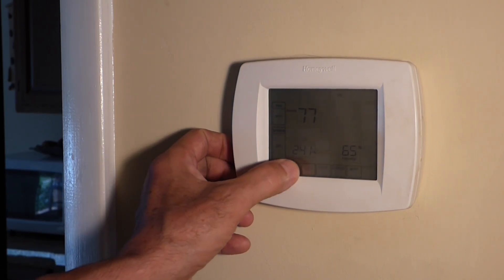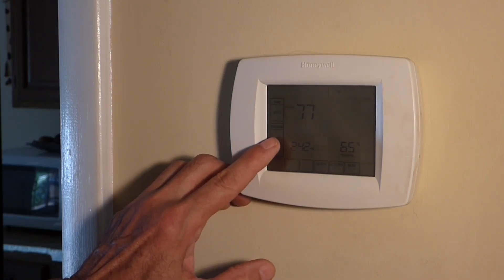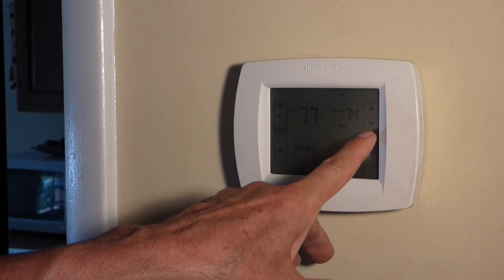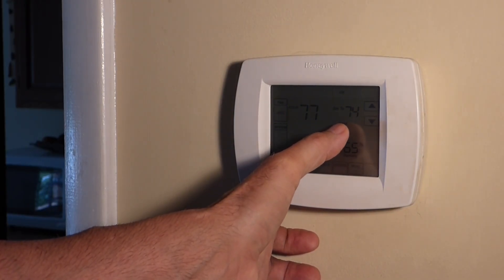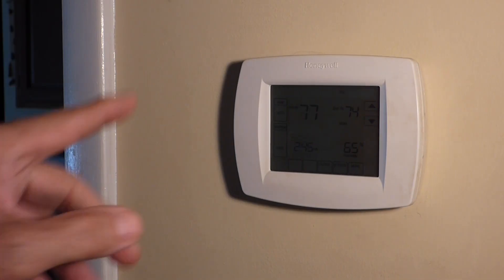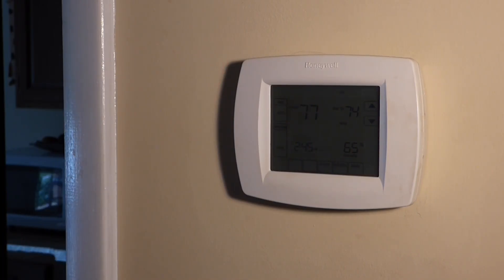Let's go in and see if the thermostat's back on. We'll touch that — it came on. And then you push this button here. It's set to off, and we want cool. We're at 77 in here right now, and it's set at 74. Now there's a little delay for the unit to reset, and we'll see if it kicks on. There's an indicator on here that says 'wait.' So I'm going to go up into the attic where the unit is and show you a real typical problem. We've been waiting here a little while and it hasn't fired up, so let's go up and check that out.